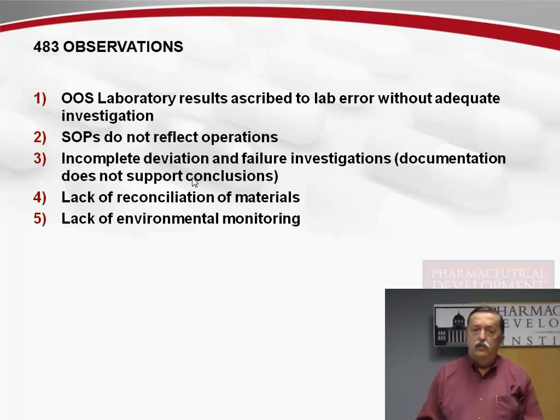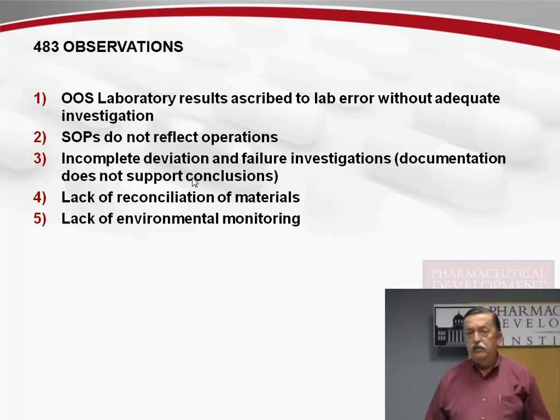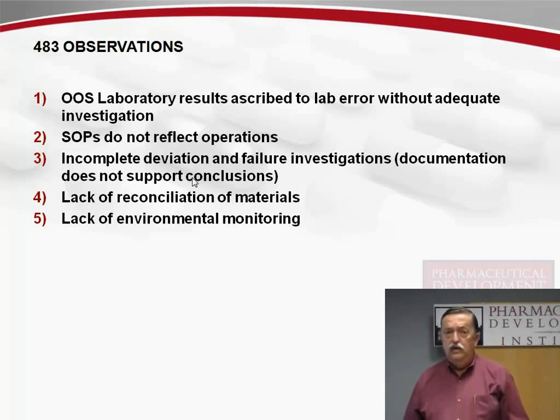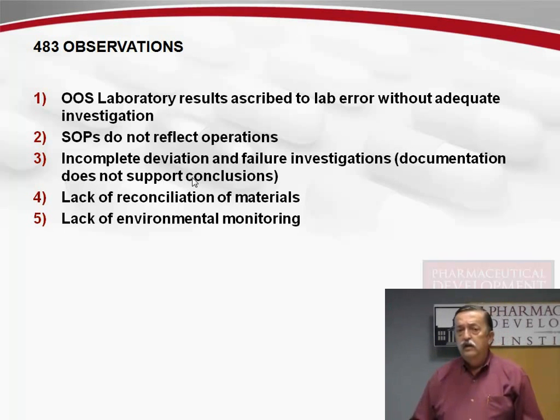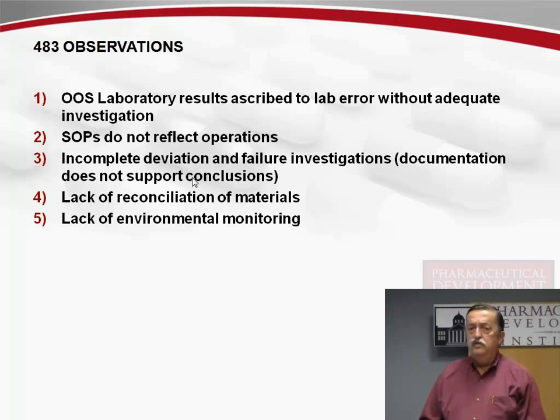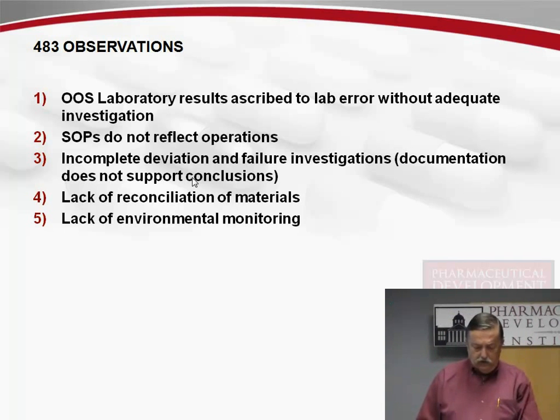One of the companies I worked with, which ended up under a consent decree, had this as the basic source of their problem. The protein solution product they sold in the marketplace was growing mold. It wasn't caught in their sterility testing, and they didn't catch it in the environmental monitoring even though there were excursions that occurred during the production of that lot. So that's something you need to critically take a look at as part of your environmental monitoring.